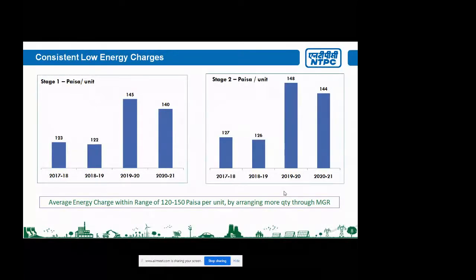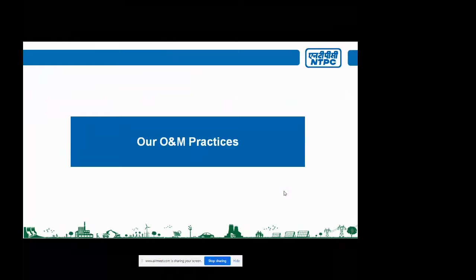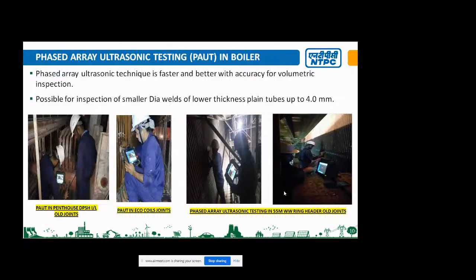As we can see here, sir, our energy charges are below 1 rupee 50 paisa. So we are committed to provide economical power to our country. Going ahead with our O&M practices, the theme for this O&M conference. Starting with our most valued equipment, the boiler, we have adopted the phased array ultrasonic testing system in our boiler checking. Phased array ultrasonic technique is faster and better, with accuracy for volumetric inspection.